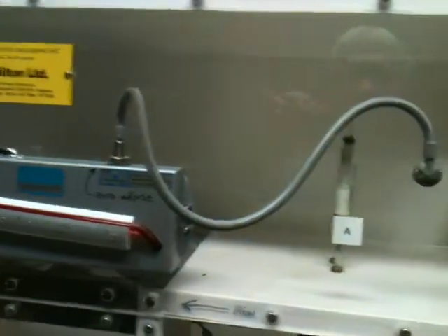Since the air is flowing past the wet wick, it cools off that thermocouple and we get the wet bulb temperature, very similar. So we go down through the static mixing blade here. There's station B, dry bulb, wet bulb. Here is the second mixer. You can see the vanes on it, stationary vanes that just impart some rotation to the flow to mix it. Here is the preheater, so electric element there.